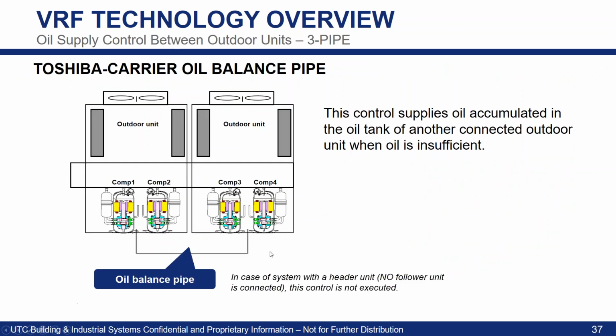Let's click through here. Something that Toshiba-Carrier has is we have a separate line for when we're connecting outdoor unit modules, which is our oil balance line. So not only is the oil shared within the outdoor unit itself, but when we have multiple module systems, there is an oil balance line that will be connected to, this showing a dual module, and then also if we were to have a triple module, we'd see another module over here where that oil balance line would be connected to that third module. So we're sharing the oil throughout that entire system.